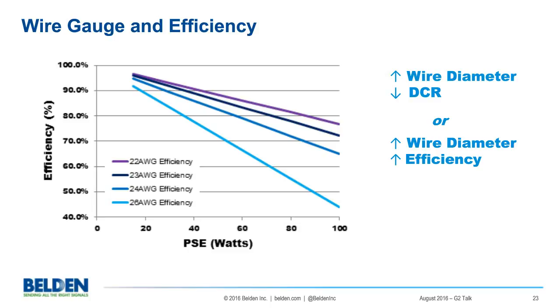For example, if I have 60 watts of power being delivered with a 23 gauge wire, I can expect around 84 or 85% efficiency. Whereas if I was to use 26 gauge wire, we would be well below 70%. So you increase the wire diameter, you decrease the DC resistance. Or another way of saying this is bigger wire diameter means better power delivery efficiency.